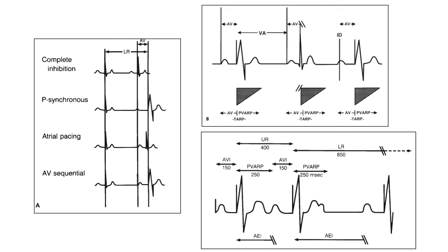Although these P waves might not be tracked, the pacemaker is capable of monitoring the events that coincide with the refractory period and recognizing the rapid pathologic atrial rates. Thus, the system at that time can switch from a tracking mode to a non-tracking mode, so that the rest of the pathologic atrial events that occur during the atrial refractory period will not be tracked.